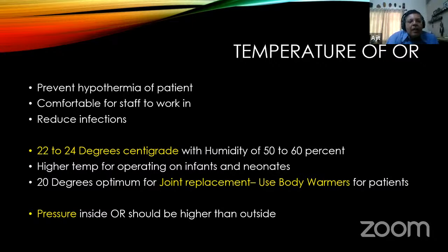The pressure inside an operation theatre should be higher than outside, so that air from the OT always flows outside through the cracks, not the reverse.